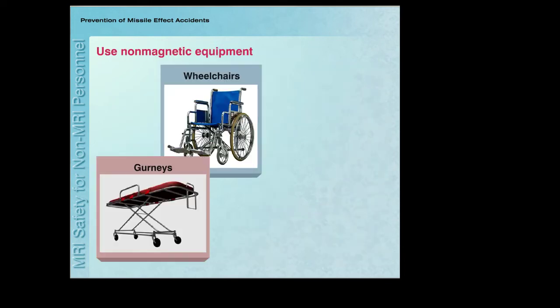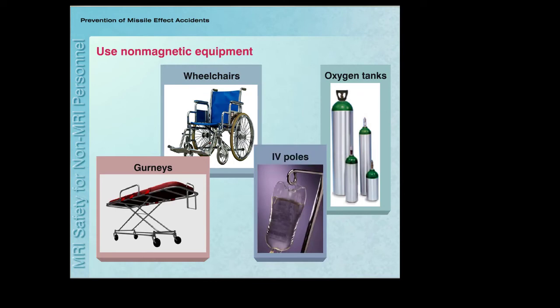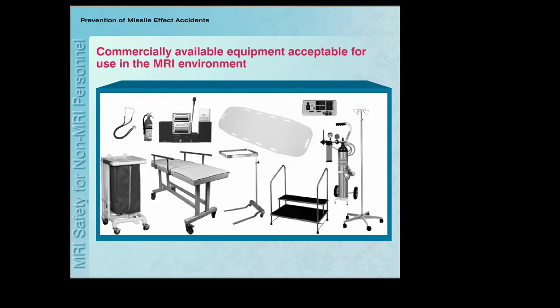If you are assisting a non-ambulatory patient into the MRI system room, make sure that the patient is using a non-magnetic wheelchair or is on a non-magnetic gurney. Inspect the wheelchair or gurney for the presence of a magnetic oxygen tank, IV pole, or other similar components or accessories before allowing the patient into the MRI system room. Fortunately, there are many commercially available devices including wheelchairs, gurneys, IV poles, instrument stands, oxygen tanks, and laundry carts that are made from non-magnetic or non-metallic materials that may all be used safely in the MRI environment.